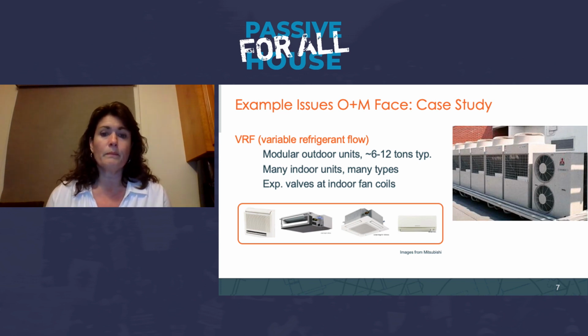So one of the main systems that we see in our passive house projects are air source heat pumps, variable refrigerant flow to be precise. What we basically have is an outdoor unit that can handle multiple indoor units or multiple apartments at once. These usually range from 6 to 12 tons in size. They can handle many indoor evaporators, anywhere from 13 to 20, depending on the manufacturer. And the indoor unit is where the expansion valves are, at the indoor fan coils.